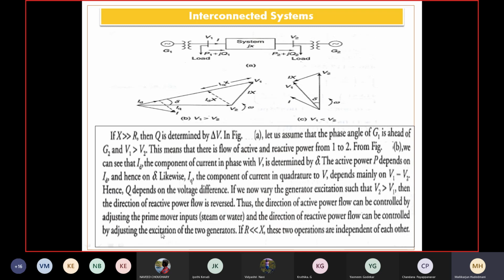So P is addressed by the prime mover, and the direction of the reactive power flow can be controlled by adjusting the excitation of the generator. So see here, ALFC and AVR are coming over here. For the control of active power, ALFC comes into the picture. ALFC will look after the active power supplement by making a mechanical supplement to the turbine. And to control the direction of flow of reactive power, AVR comes into the picture. That AVR looks after excitation control of the generator.